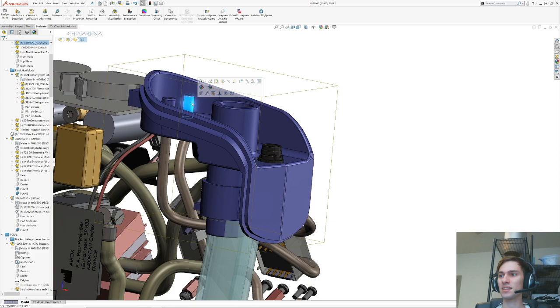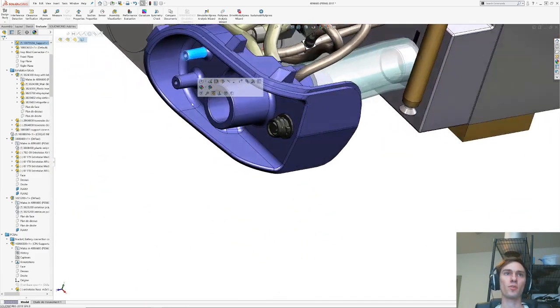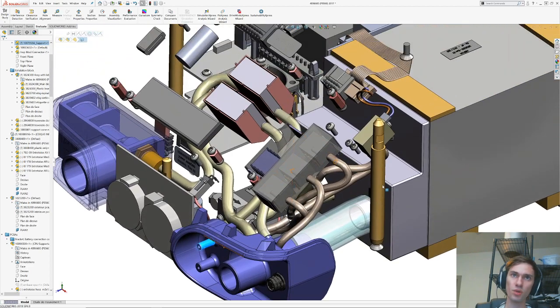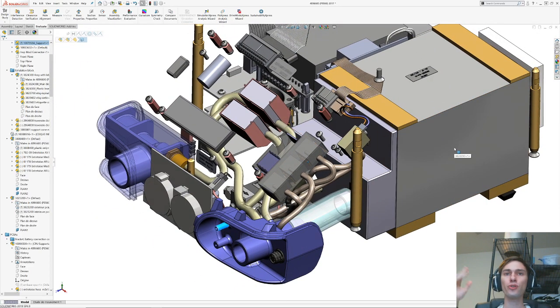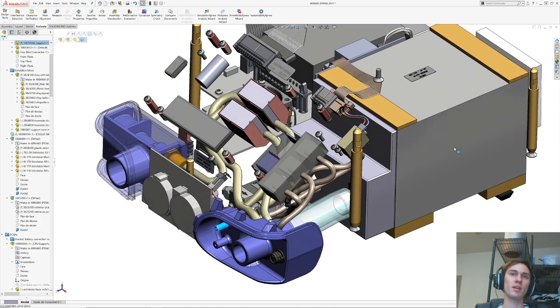You only need 10 liters per minute max. JK, it's like 6 liters per minute max. So Braden, the thing is that you have to remember the duty cycle, right? So because this is continuous positive pressure, it can do 580 liters per minute, but if you take 12 breaths a minute, that's like a fifth of a cycle. So that means that it's only producing 100 liters a minute.